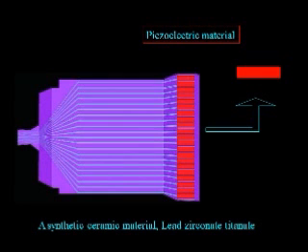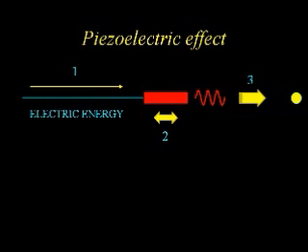How are ultrasound beams generated and how do we form an image using ultrasound? This image shows a transducer which we use to scan patients during ultrasound. This transducer is made up of multiple small crystals. These red crystals are ultrasound-generating crystals. They are basically a synthetic ceramic material named lead zirconate titanate, and each probe contains multiple crystals.